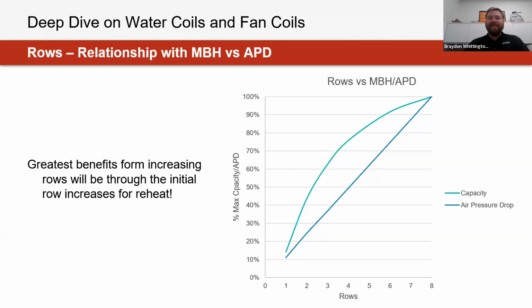It's the relationship of diminishing returns. I see a question here too from Jonathan: what's the most rows you've seen on a single coil? Well, from the terminals and fan coil side of things, I would say 10 rows of coil. So 8 rows of cooling and 2 rows of heating is a typical one that we might see. I know it could potentially get much bigger when we're talking about air handlers or different equipment within industry, but I'd say that's the most typical maximum of what we'd see: up to 8 rows for cooling and up to 4 rows for heating.